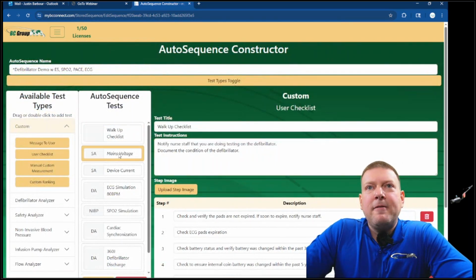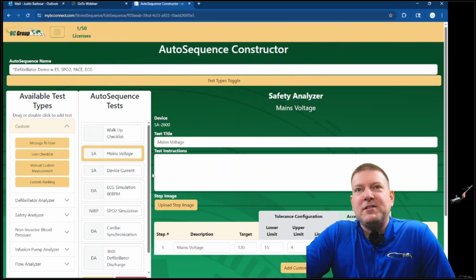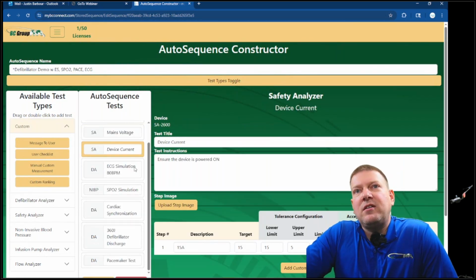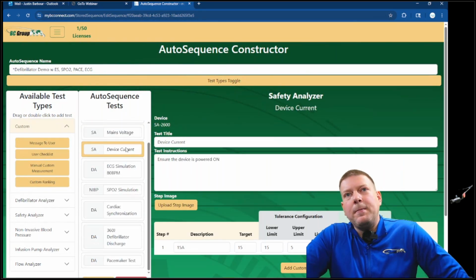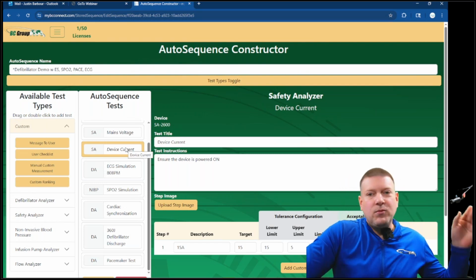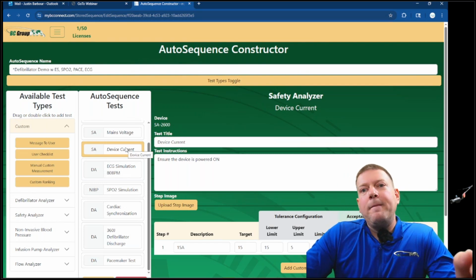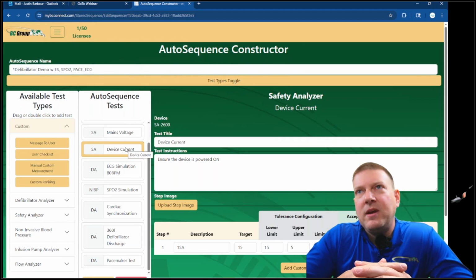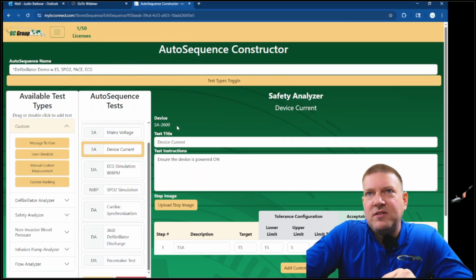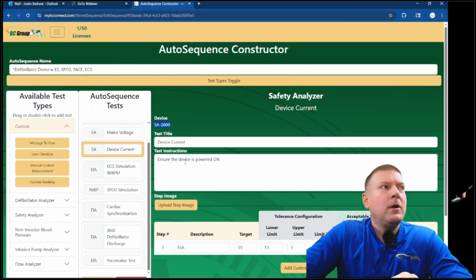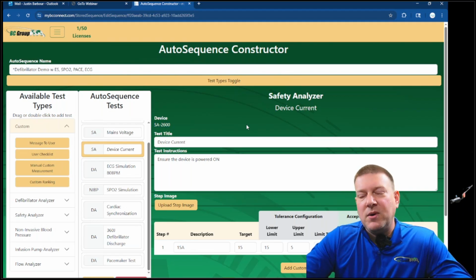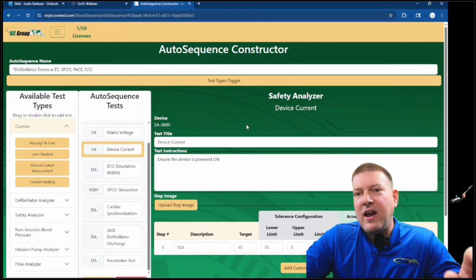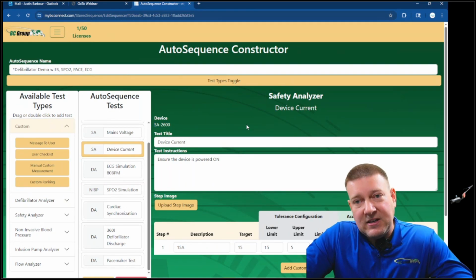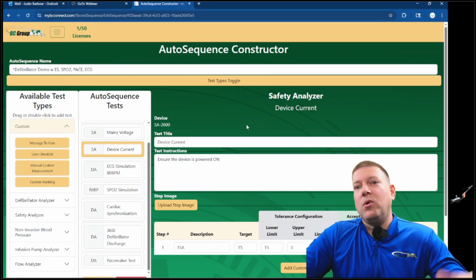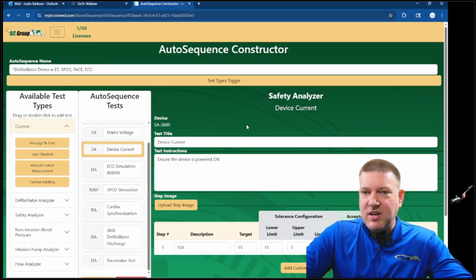And then I have regular electrical safety stuff, guys. So mains voltage check, device current, and when I run this test, which I have an example over here, the electrical safety meter, because I currently have it set up for the SA2600, which you can see right up here, it can automatically start doing this stuff without requiring any sort of interaction from the technician. So as long as they hook it up according to the image, you proceed with the test.